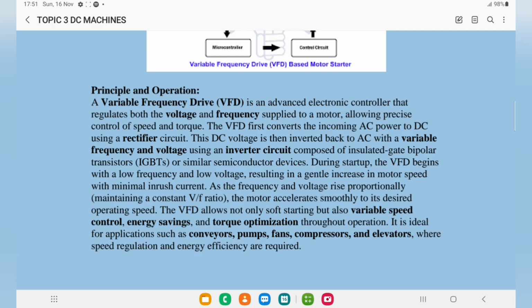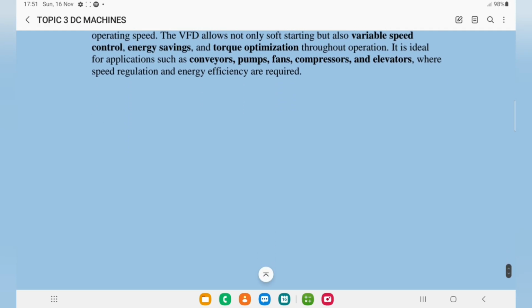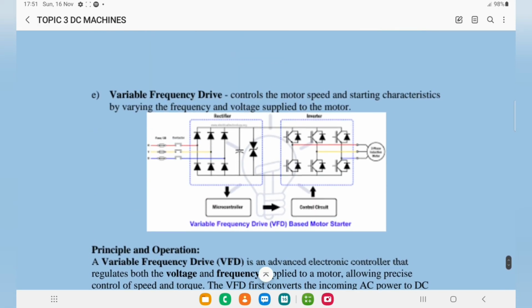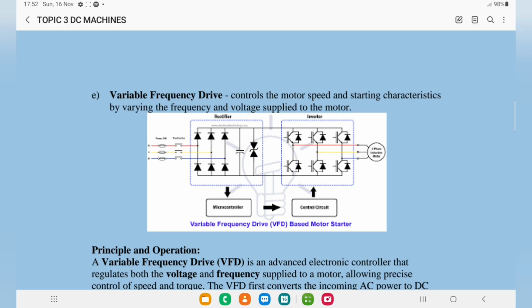The VFD allows not only for soft starting but also variable frequency control, in terms of energy savings and torque optimization throughout the operation. This method is ideal for applications such as conveyors, pumps, fans, compressors, and elevators, where speed regulation and energy efficiency are required. Those are the three-phase motor starting methods that you're supposed to know.